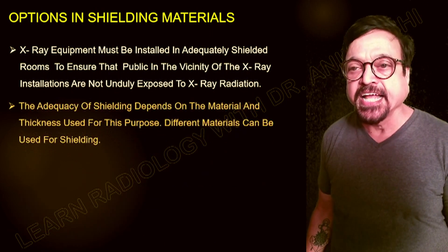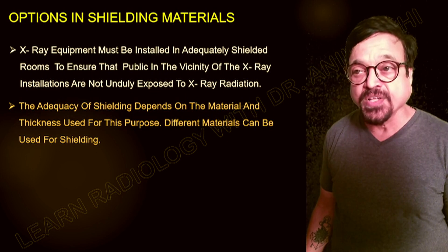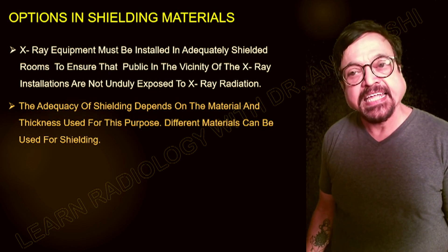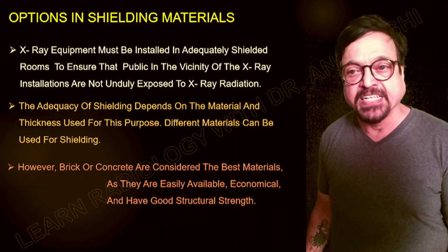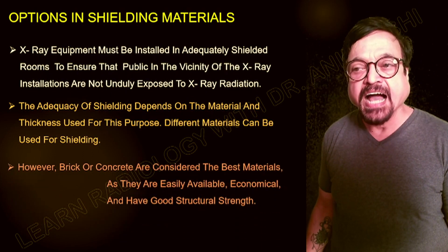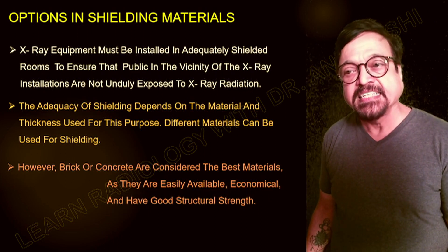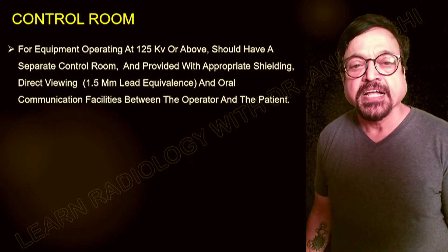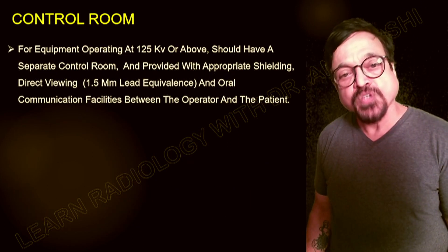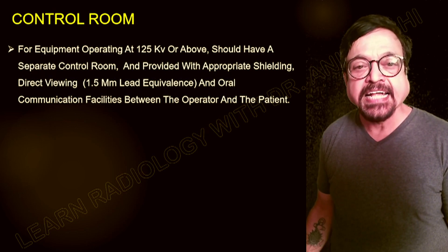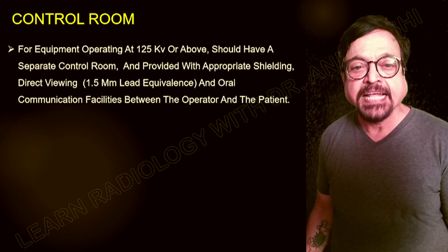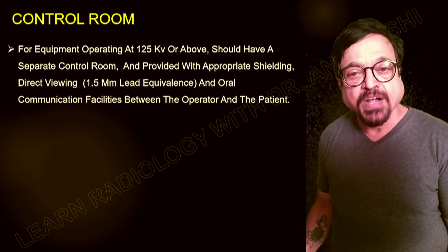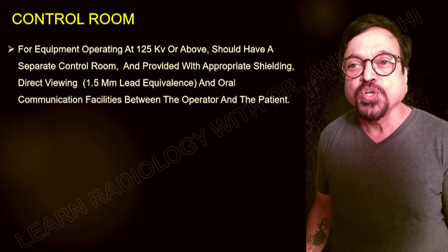The adequacy of shielding depends on the material and thickness used. Different materials can be used depending on convenience; however, brick or concrete are considered the best materials since they are easily available, economical, and have good structural strength. For equipment operating at 125 kV or above, there should be a separate control room. Most diagnostic x-ray units do not go up to 125 kV, but if the unit does, a separate console room is required.